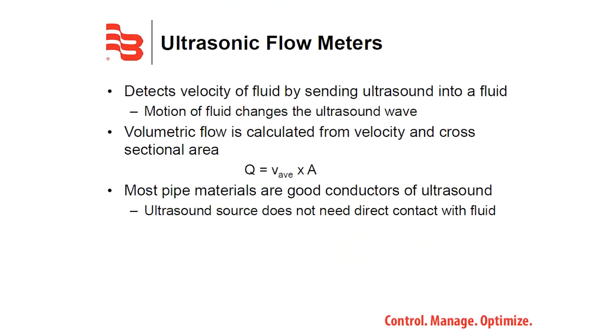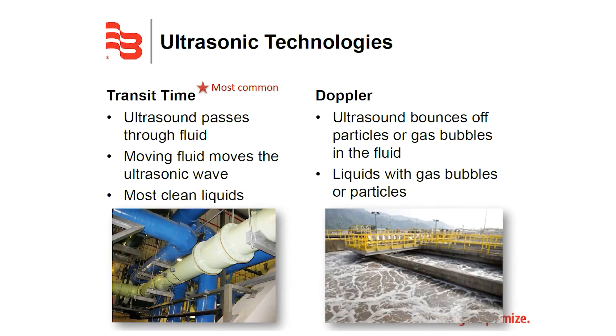Ultrasonic flow meters use sensors strategically mounted on a pipe to send and receive ultrasound. Together, these sensors calculate the velocity of the fluid inside the pipe. With velocity and cross-sectional area, you can calculate volume.